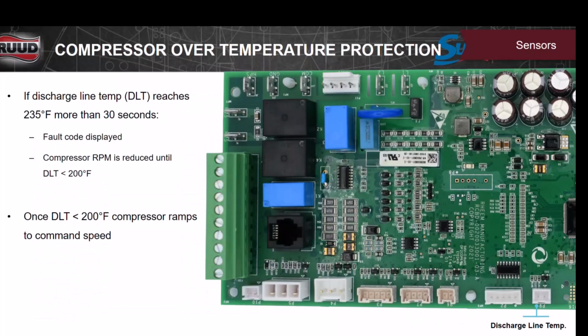Discharge line temperature on the outdoor unit: if it reaches 235 degrees for more than 30 seconds, it will display a fault code that says discharge line temperature high, followed by, of course, D_O. But the compressor at that point will lower its RPMs until we get below 200 degrees. When we fall below 200 degrees, it goes back to the command speed.